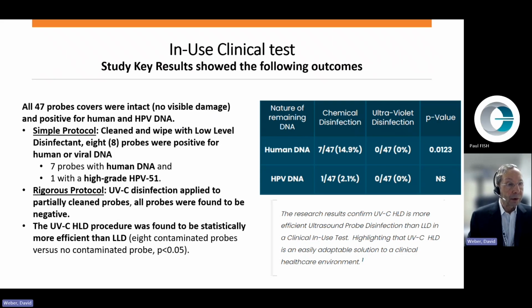All 47 probe covers were intact, with no visible damage, although, as we've already seen, they can often be damaged, and positive human and HPV DNA. Simple protocol, cleaned and wiped with low-level disinfectant: 8 probes were positive for human or viral DNA, 7 probes with human DNA, and 1 with high-grade HPV 51. Now, with the rigorous protocol, UVC disinfection was applied only to partially clean probes. All probes were found to be negative. The UVC HLD procedure was found to be statistically more efficient than low-level disinfection, with a p-value less than 0.05.